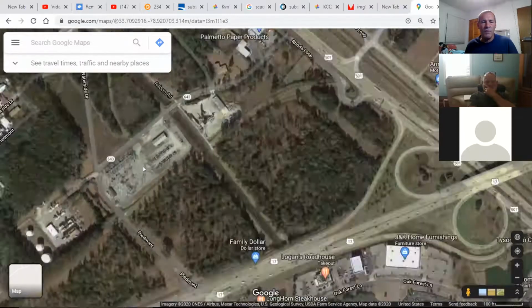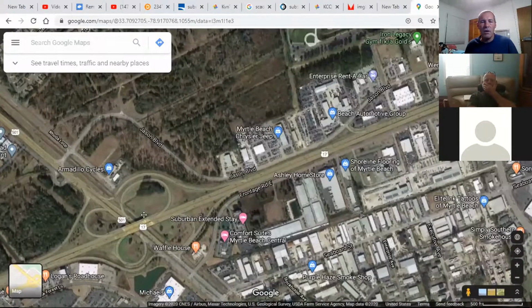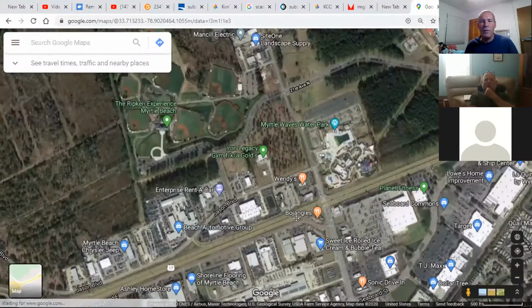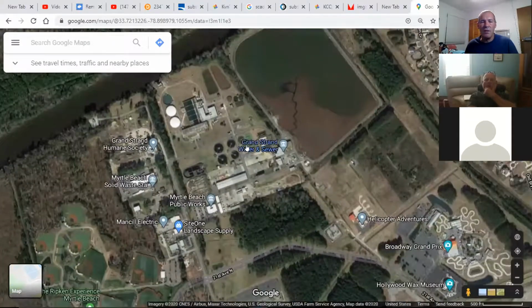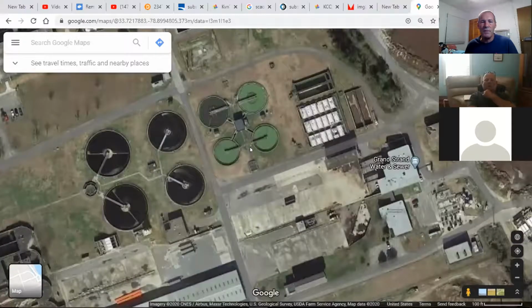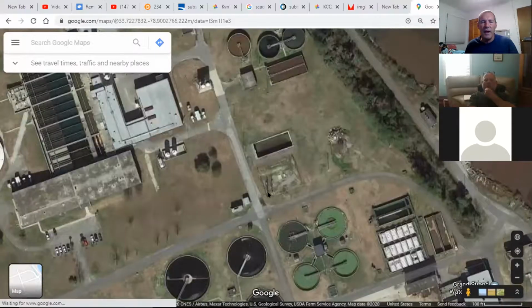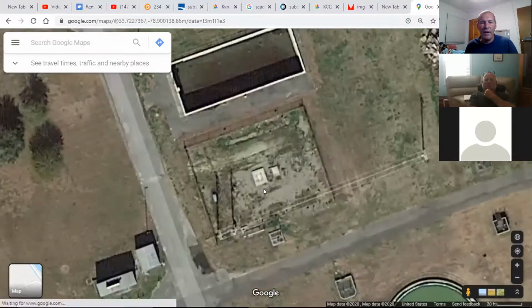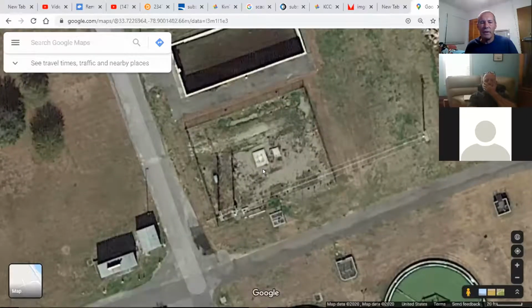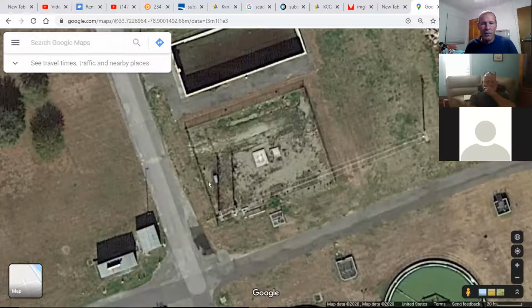One circuit comes out of here and is dedicated. No other attachments to it, all the way to Grand Strand Water and Sewer. The nice thing about this right here, gentlemen, and the substation does have battery backup. If I lose the 34 kV line, sorry, I can't drive in here. There's two set of switches. There's one actually that you can see right here that's a recloser. I can open this recloser and close a switch right here and actually feed this substation automated.